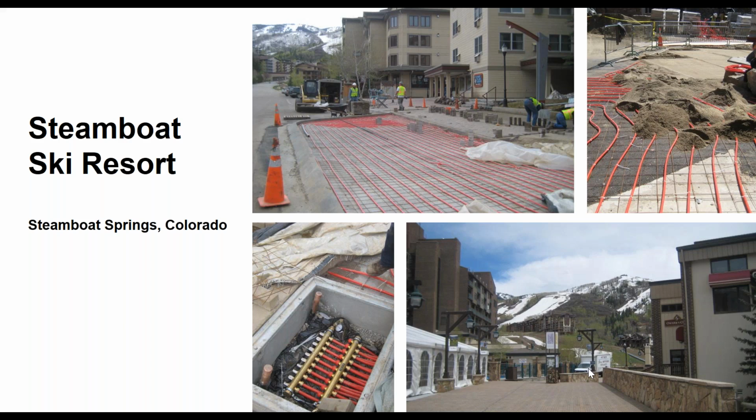Placement of the sensors. The worst conversations to have about snow melt sensor placement is when you go to a job site and it's not working right, and you say, well, where's the snow melt sensor? And then the person who did the system is holding it in their hand still. That's a problem, because then you have to core drill that into the slab. You want it in the melted area as a general statement. It has to be somewhere between these pipes, or else it's not going to melt itself clear.